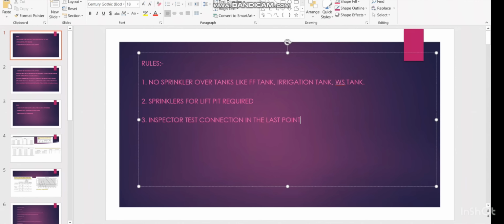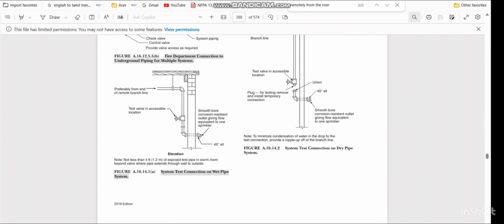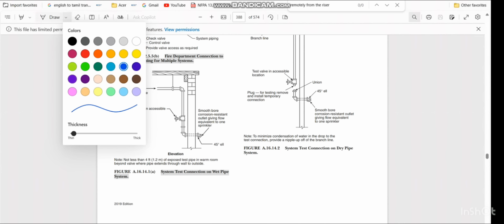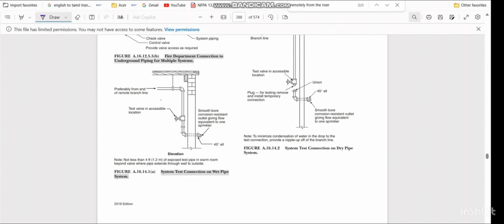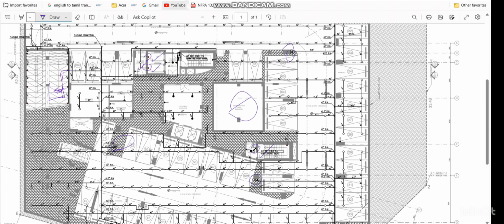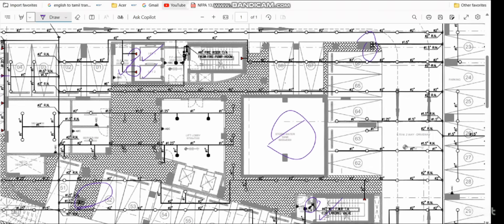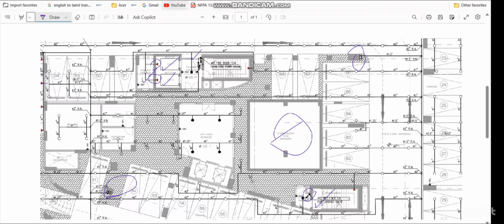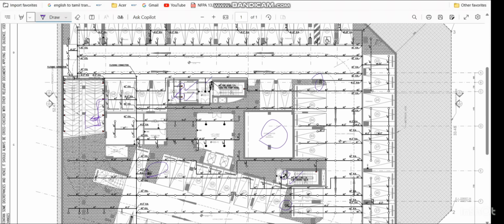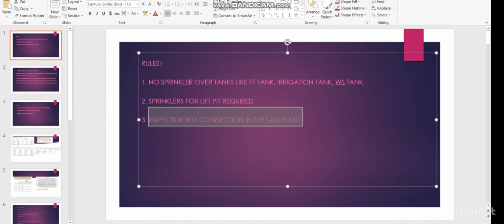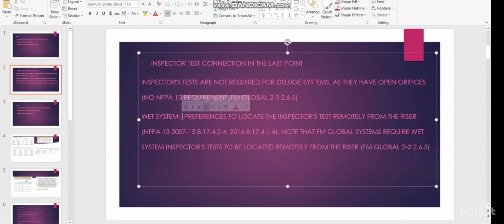And the next important thing is the inspector test connection. First we will see what the inspector test connection is. Here you can see in NFPA 13 they have given the inspection test connection details. Preferably from the end of the remote branch line, we have to take the connection like this. Here we have to provide the test valve, the inspection test valve, and it will be connected to the nearest drain. So in our project, for example, here you see we have one riser here. And from here we have to see the end point of the project. So we have 2 rules, which I have highlighted here.